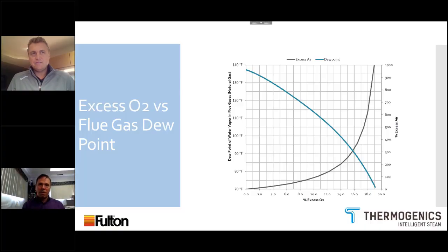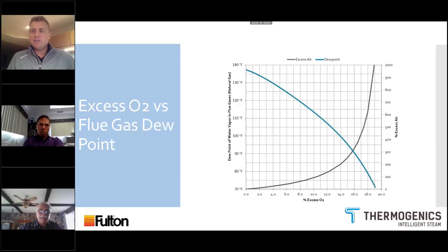Turn down is great, but it has to be true. And as you note with steam boilers, the suggestion of perhaps adding O2 trim is applicable only to certain appliances. Even big boilers, depending on the pressure drop across that appliance, like I'm talking large fire tubes, there's only so much O2 you can scrub at that point. So make sure you have a conversation with your vendors to ensure you're getting what you pay for.